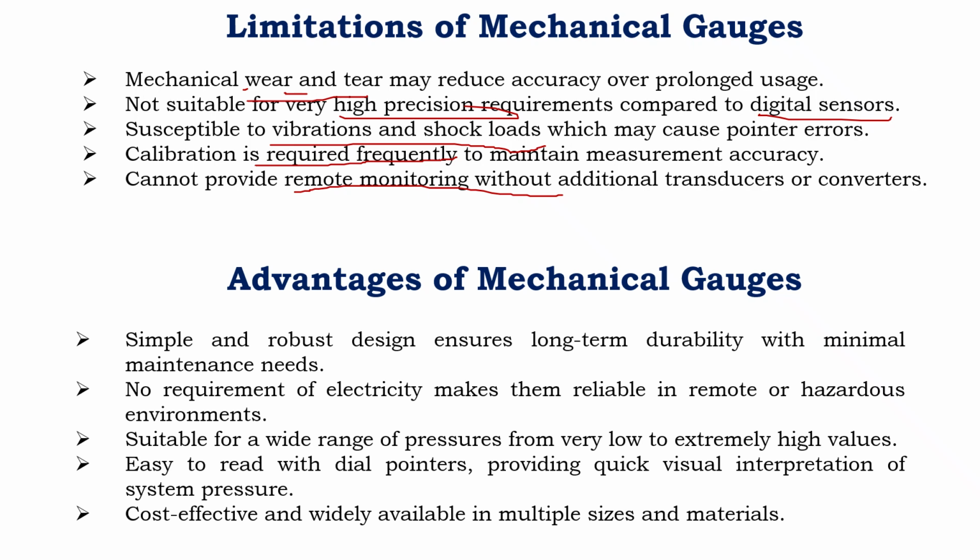But there are also some advantages of mechanical gauges. It is a simple and robust design, and minimal maintenance is required. There is periodic maintenance, but even so, only minimal maintenance is needed. It also works for the very long term. Even for 50 years, if you maintain it properly, it will work properly, and it doesn't need any electricity. No electricity is required, and it is reliable in remote or hazardous environments.